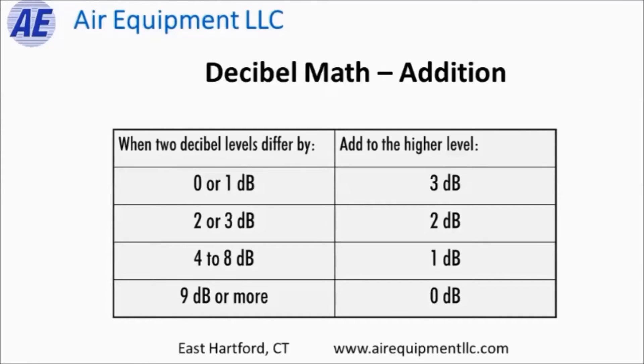So for example, one noise source at 50 and one at 49: take the louder one, 50, add three, and the net effect is 53 decibels. If the difference in decibel levels is two or three, take the louder one and add two. If the difference is between four and eight decibels, take the louder one and add one decibel. If the difference is nine or more, just take the louder noise source and that's it — because when you have two sources and one is ten or more decibels louder than the other, it is completely drowning it out.